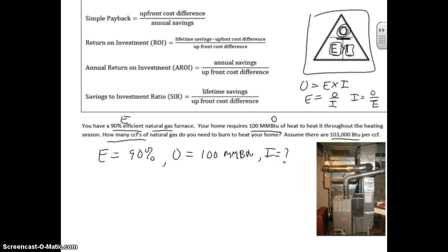Let's start with our equation. Our input equation is output over efficiency. Our output is 100 mmBTU, and using our knowledge of metric prefixes, we know that that's 100 times 10 to the 6th BTU. So let's just plug and play here. 100 times 10 to the 6th BTU divided by the efficiency, which is 90%, which is 0.90.